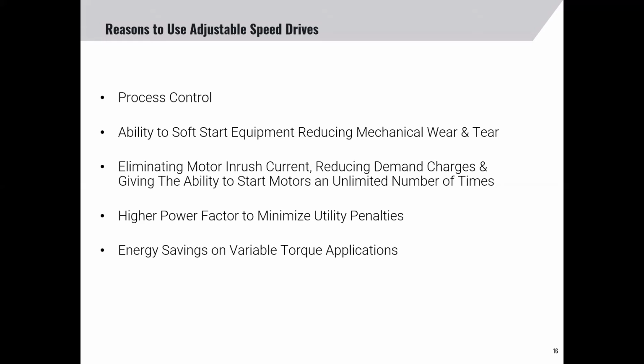You also have a little bit more operational control. Every system has some kind of resonance. A variable frequency drive will often allow you to move past any critical frequencies you may have in your system without landing and staying on that critical frequency, causing unwanted vibrations and causing your system to begin to resonate.